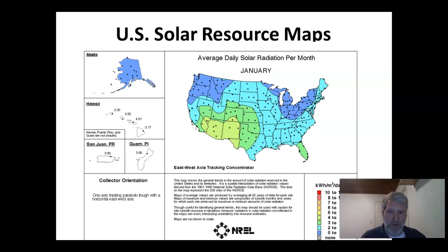Here is our solar resource map. So we have the average daily radiation or insolation that we're using, and we have this measurement called a sun, which is a kilowatt per meter squared per day. And our solar panels are rated at this too with our STC. So you'll notice here in Portland, Oregon, we are in the 0 to 2 rating. We're actually pretty much right at 2, depending on the coldest month.